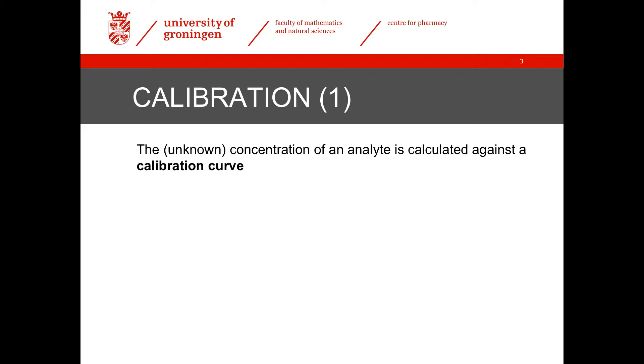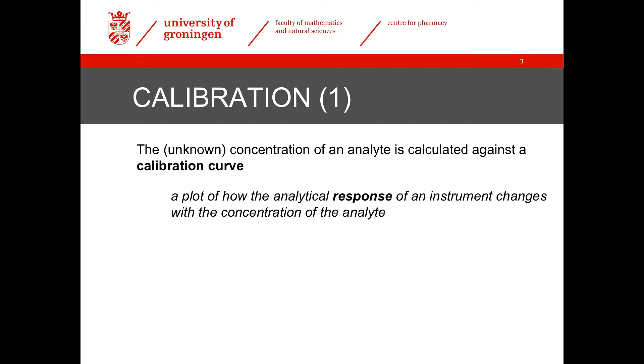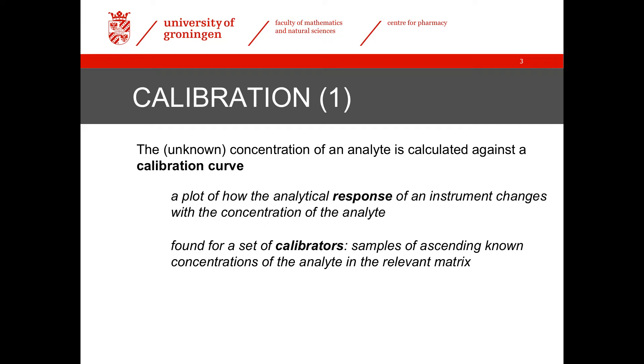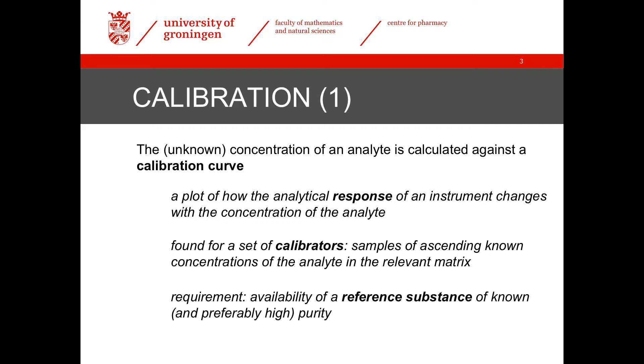The basic principle of calibration is that a set of calibrators with known concentrations is analyzed, and that the unknown concentration in a study sample is calculated by comparing its result to the results of the calibrators. We do this by measuring the response of the instrument for each of the calibrators, which, as was discussed earlier, are samples with known concentrations of the analyte in the relevant matrix. And we need a proper reference substance to make the calibrators.